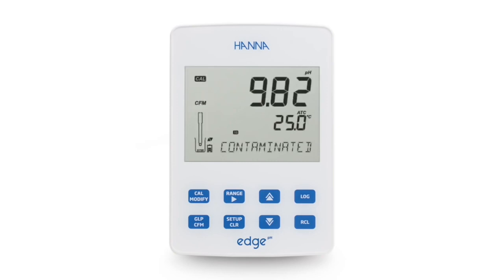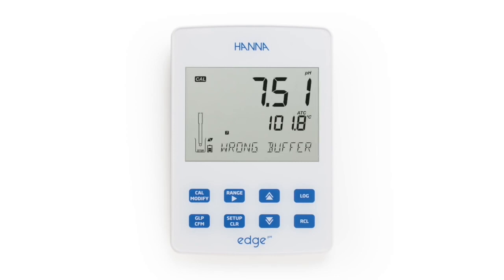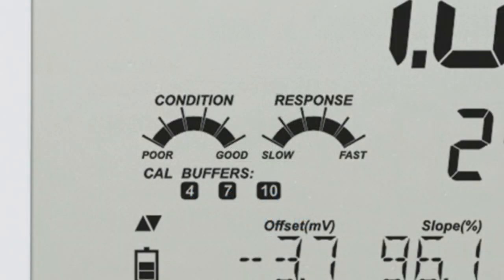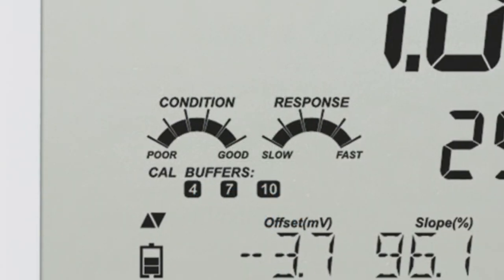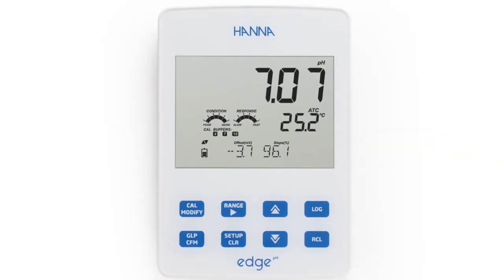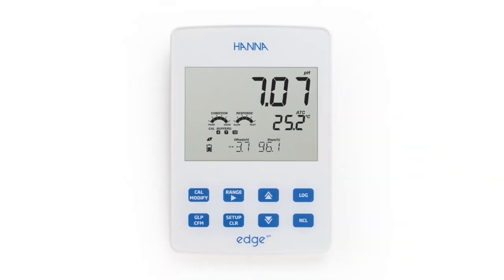CalCheck monitors electrode behavior over time and uses this data to alert the user of potential problems, such as a dirty electrode or contaminated buffer solution. The HI2002 will also alert the user if the temperature of the calibration buffer is out of range. After calibration, the overall electrode condition is displayed on the measurement screen. CalCheck ensures stress-free, accurate, and reliable measurements.